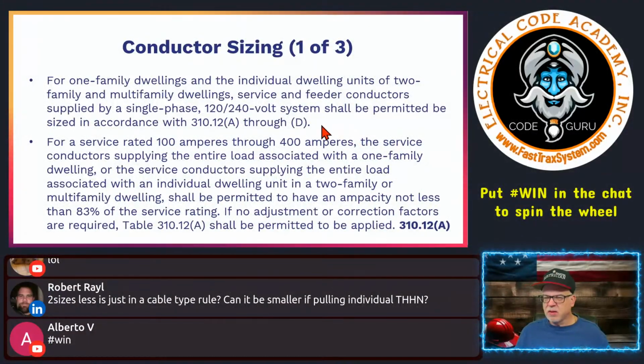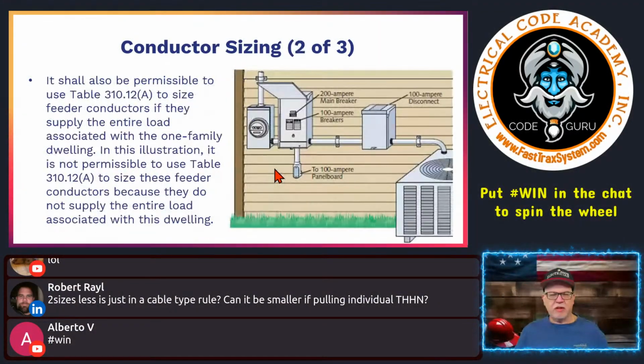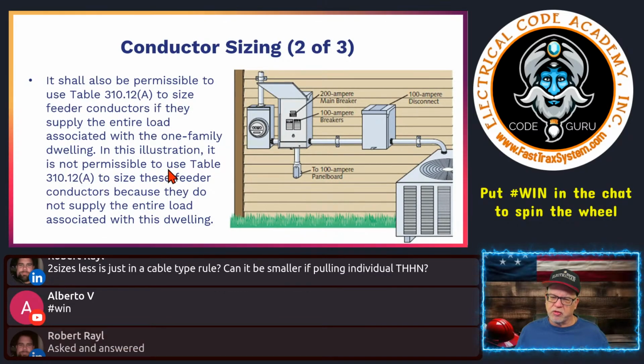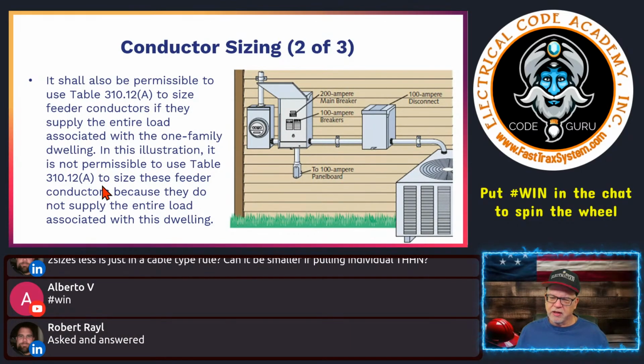All right, where was I at? All right, so let's look at this right here, get a good understanding of what we've got going on, right? So it shall also be permissible to use Table 310.12(A) to size feeder conductors, okay? So as we said, there's also a B. There's an A for service, there's a B for feeder. Size feeder conductors if they supply the entire load associated with the one-family dwelling, okay?